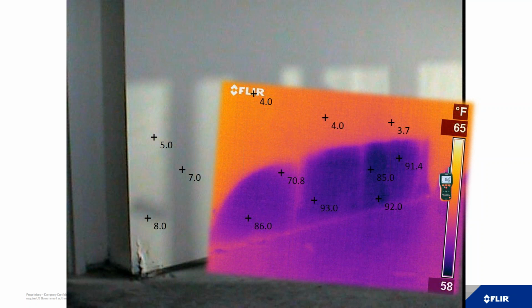Why? Due to evaporative cooling. When water goes from a liquid to a vapor, it's cooling the target that it's on, in this case the wallboard, and it shows up as a cold area. The only difference is you still need the moisture meter to confirm that it's wet.